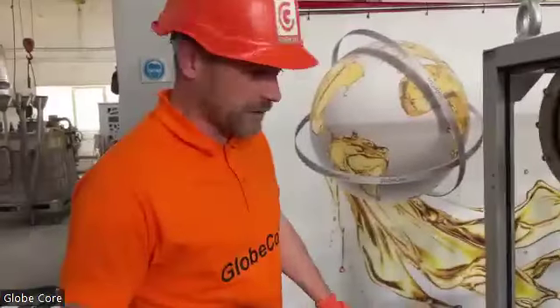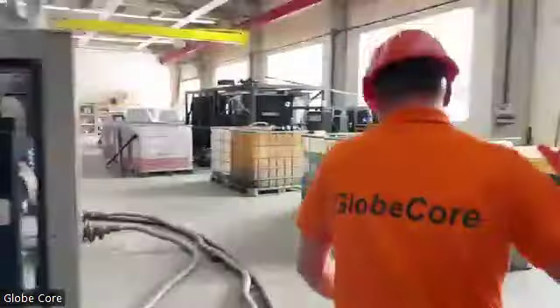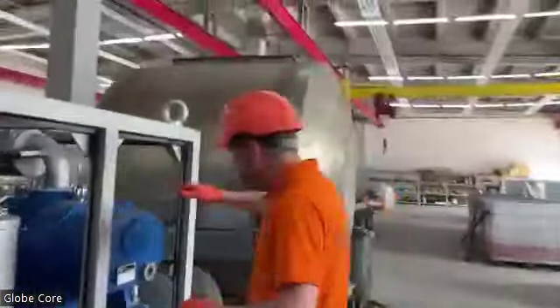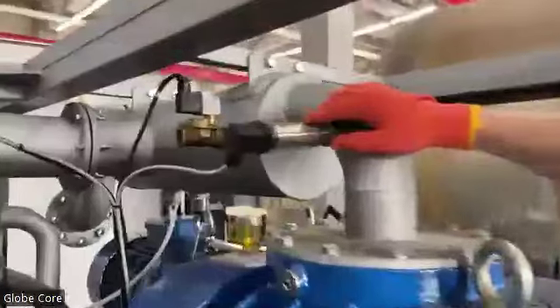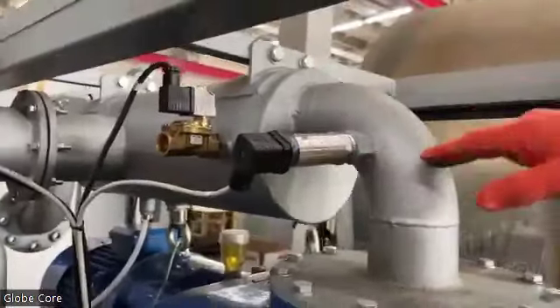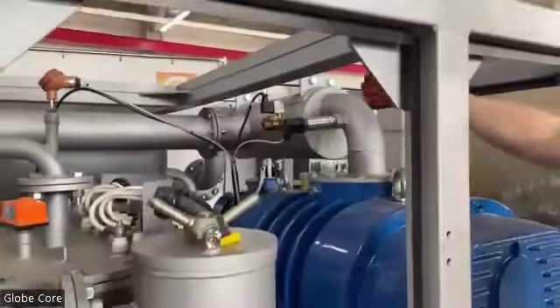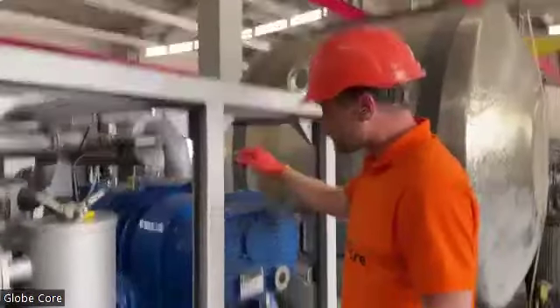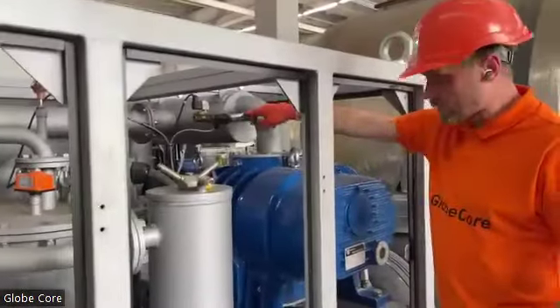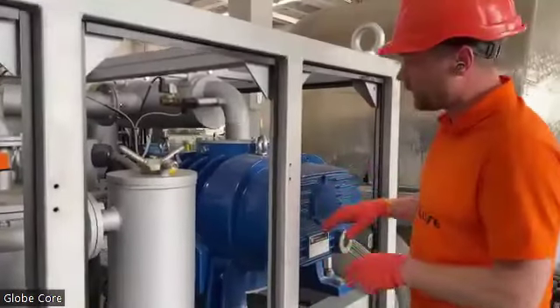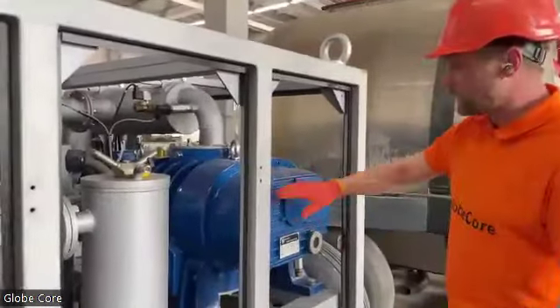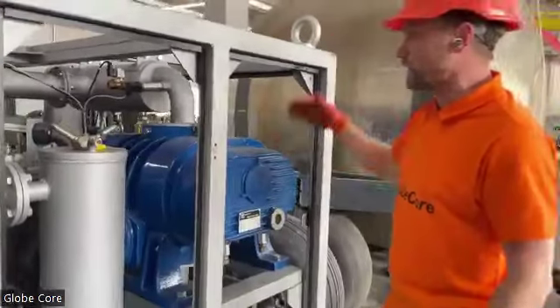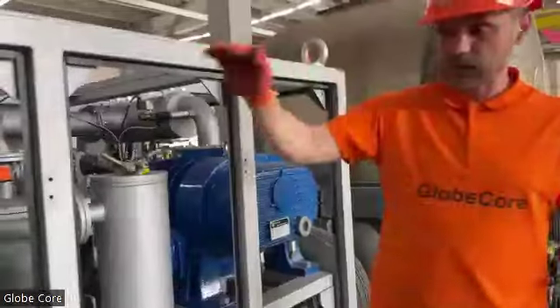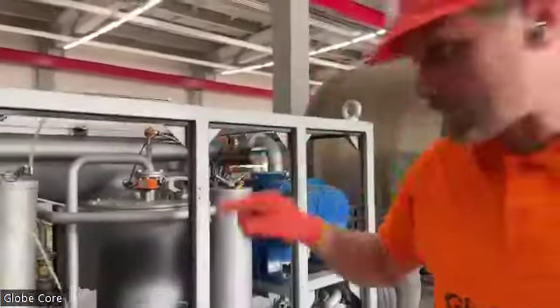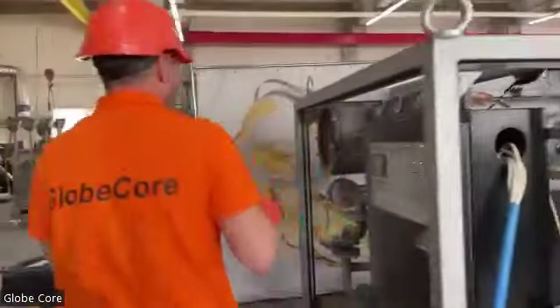Now, about other sensors. We have the vacuum sensor. It's over there. So by means of the sensor, we control pressure in the vacuum line and in the vacuum chamber. It also controls the turning off and turning on point of the booster pump. The booster pump starts when pressure is lower than 10 millibars. This setting is done on the controller of the unit.